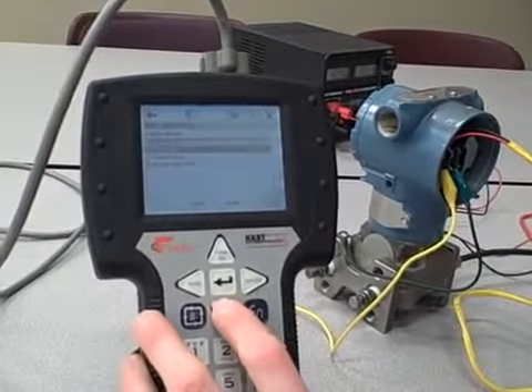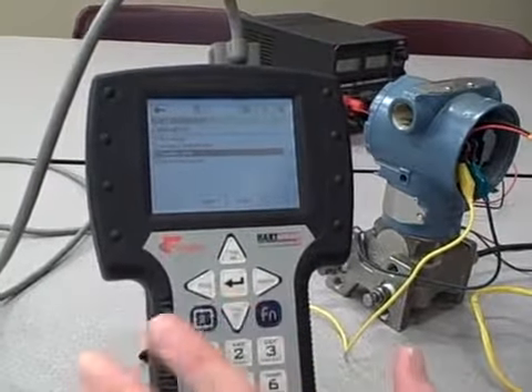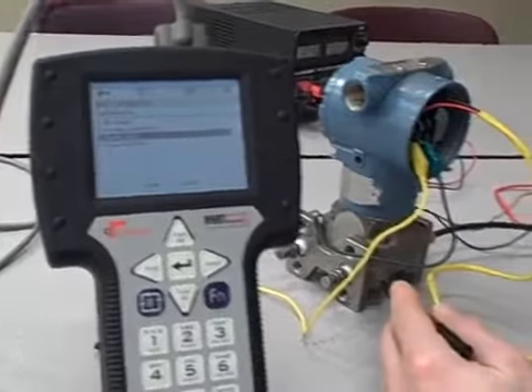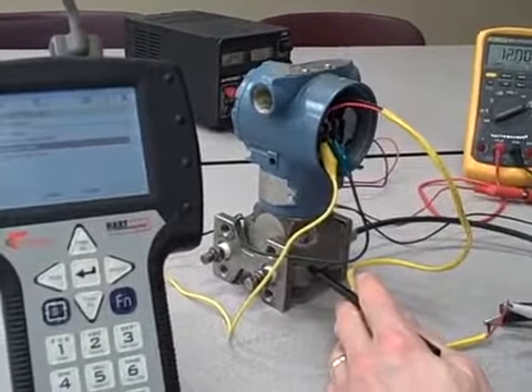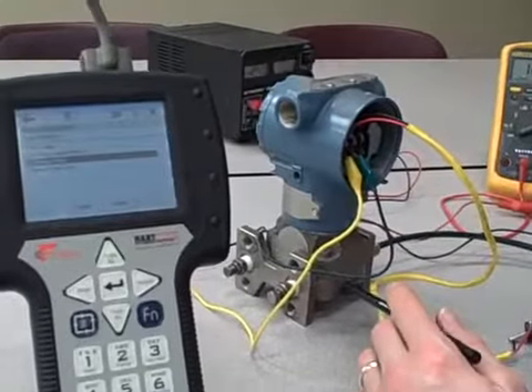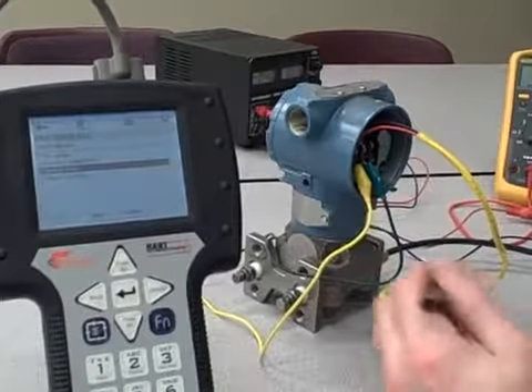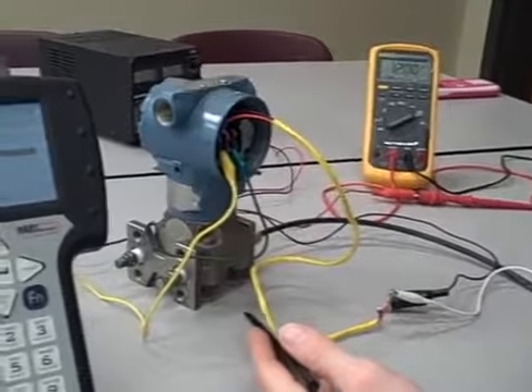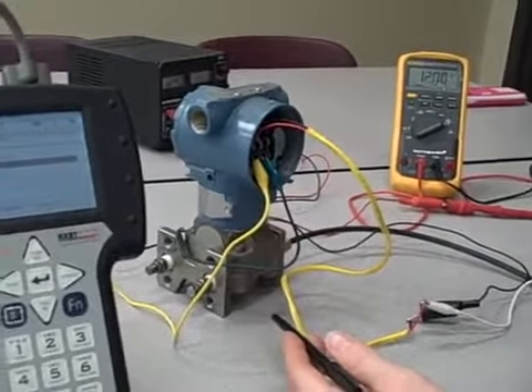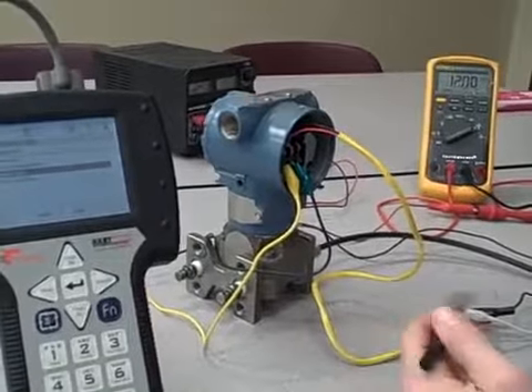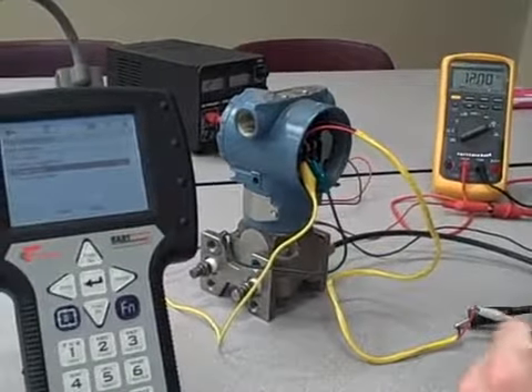We can also do a sensor trim. That's where we tell or confirm to the transmitter what certain amounts of pressure actually look like when applied to the cell. In order to do a sensor trim, I would need, in addition to the transmitter and a source of pressure like this pump, some other independent pressure measuring instrument that I could use as a standard. I do not have that on this test bench, and so I will not use that.